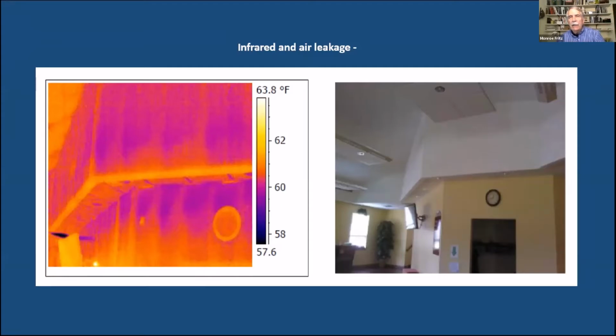Tracing the digital image over to the window on the left, when we got up there and looked around, we found that where the old building and new building were joined, there was a break in the air barrier allowing almost unlimited exterior air infiltration into this bulkhead. On this particular day it was only about 35 to 40 degrees outside, so all that was really happening was an additional load on the furnace because of the cold surface of this bulkhead and the walls directly below it.